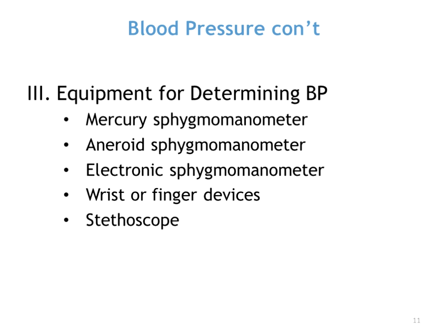Then you have your aneroid sphygmomanometer, which is an analog, and that's a compact, portable, glass-enclosed gauge with a needle for registration of the blood pressure, and it requires regular calibration to keep accurate. There are electronic or digital sphygmomanometers, and those are automatic determination of blood pressure without the use of a stethoscope.